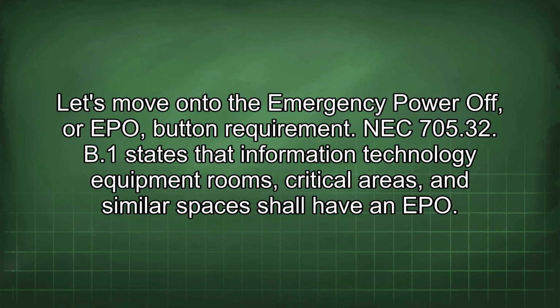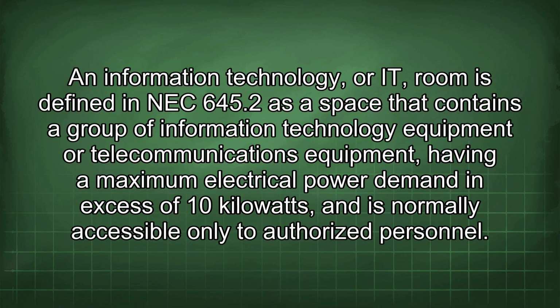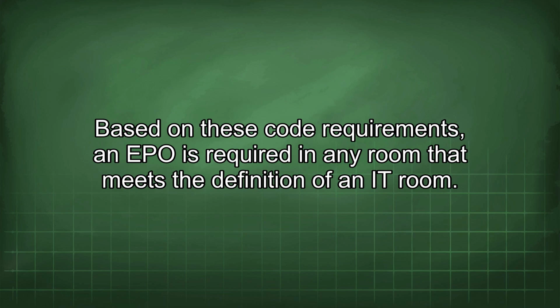Let's move on to the emergency power off, or EPO, button requirement. NEC 705.32 B1 states that information technology equipment rooms, critical areas, and similar spaces shall have an EPO. An information technology, or IT, room is defined in NEC 645.2 as a space that contains a group of information technology equipment or telecommunications equipment having a maximum electrical power demand in excess of 10 kilowatts and is normally accessible only to authorized personnel.